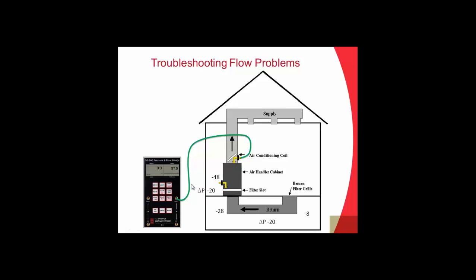So now we're measuring on the supply side. So now we're on the positive side. We're at plus 97. We're below the air conditioning coil. So this is the pressure on the supply side of the furnace. And then we'll connect up to that tube below. And now we're measuring the pressure across the furnace fan. So now we're seeing a positive pressure of 97 and a negative pressure of 48. The difference between those is 145. So we've got a change in pressure of 145 pascals across the furnace fan.